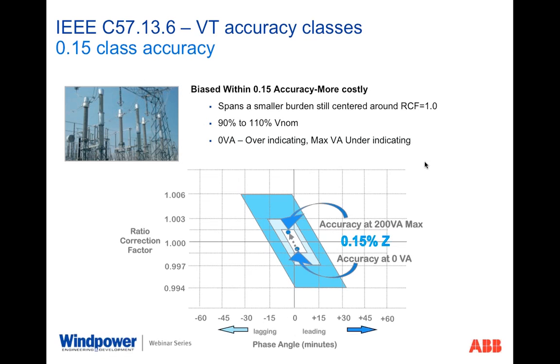So that's some of the reasons why we don't see as many inductive voltage transformers being purchased in high accuracy as we do current transformers, because they have less of an impact on the overall accuracy performance, because basically accuracy is controllable in inductive VTs.